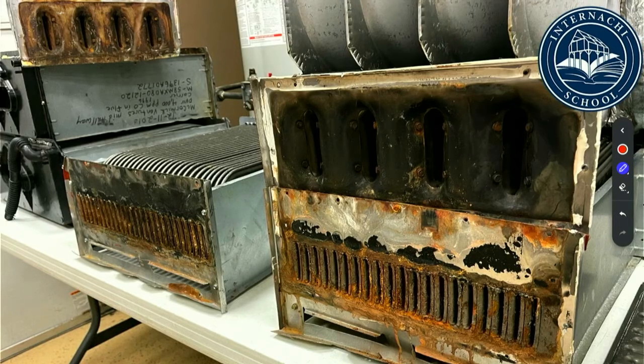These heat exchangers, these are secondary heat exchangers that we're looking at. And these all came from Carriers. All right, I know it's upside down, but you can see Carriers here. This was common for their high efficiency units. And James, if I can impose on you to write down: Carrier units manufactured 2012 and earlier. They had a known problem with their secondary heat exchangers. These things, and you can just see how that condensation from everything has just been rusting them out. And what happens is that moisture and liquid actually leaks onto the floor of the furnace.